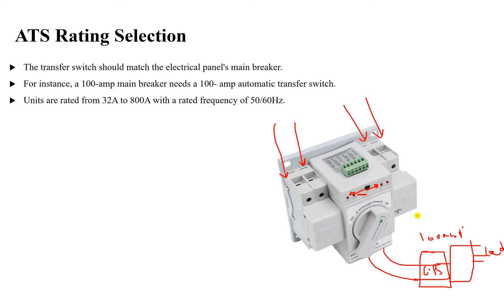ATS ratings are available from 32 amperes to 800 amperes, with a rated frequency of 50 to 60 Hz. There are also some types of ATS that can reach up to 4000 amperes for diesel generators. In this lesson we talked about the automatic transfer switch and how to select it.